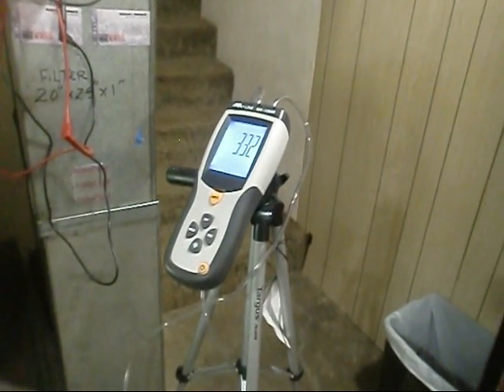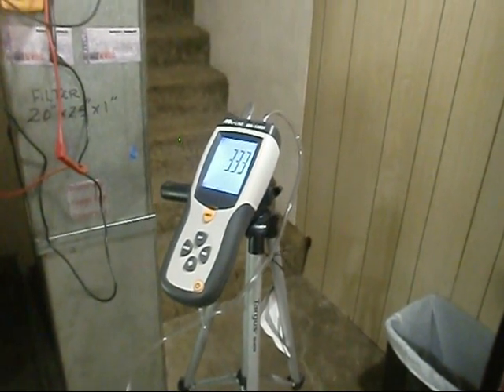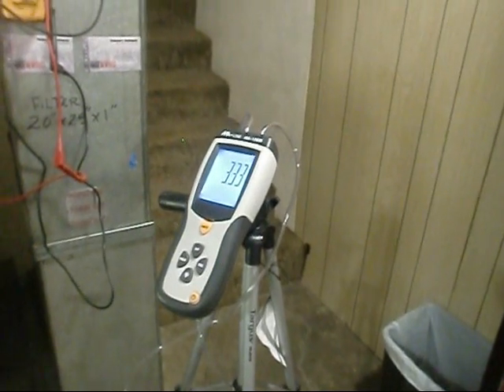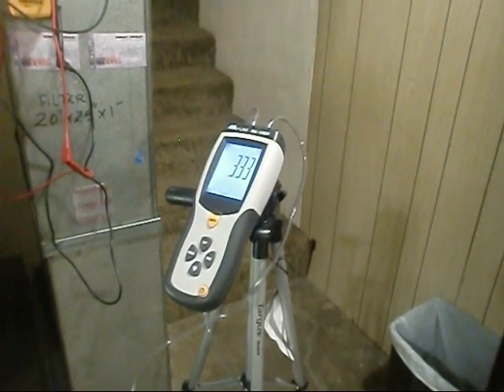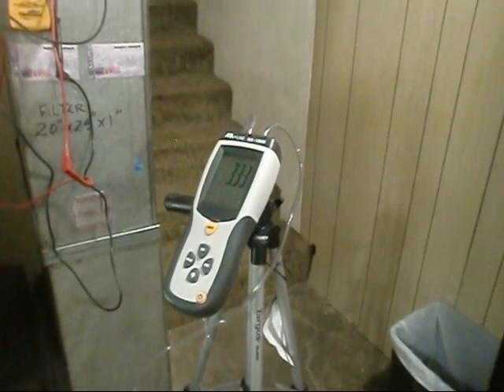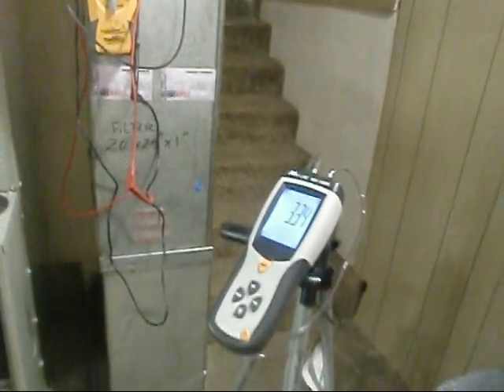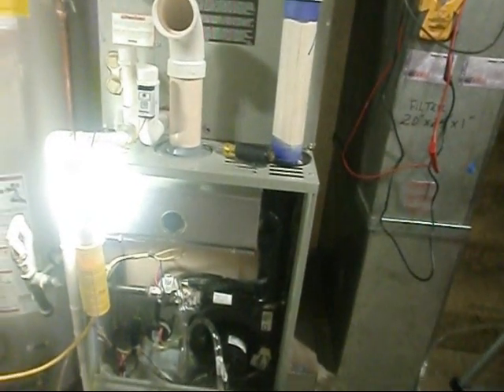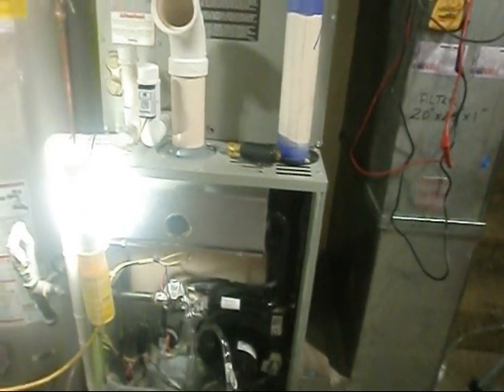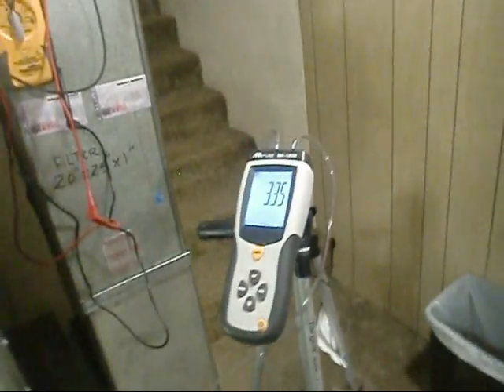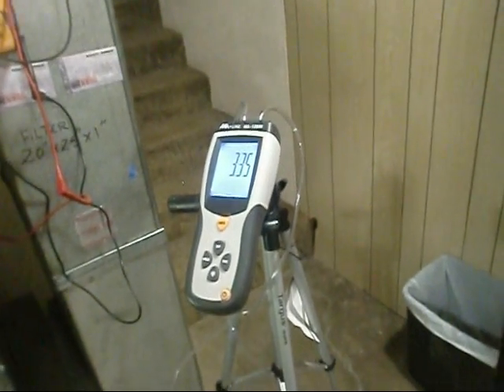It's kind of low. Does it go up after it comes on or something? Well, would you think the blower might have anything to do with that? I wouldn't think so. No, okay, you're absolutely right. When we do 90% furnaces, we need to either remove the reference tube or remove the burner box cover right here. Now let's let it kick on, just to prove to everybody it ain't got nothing to do with the blower.